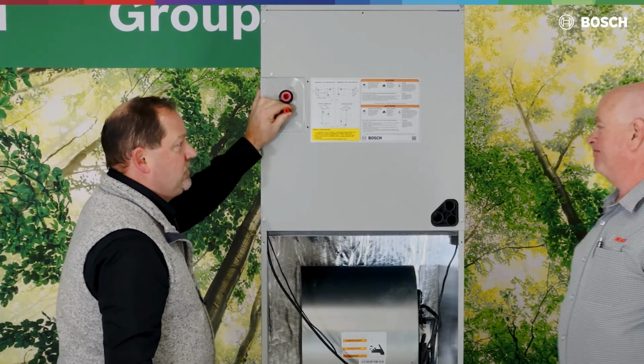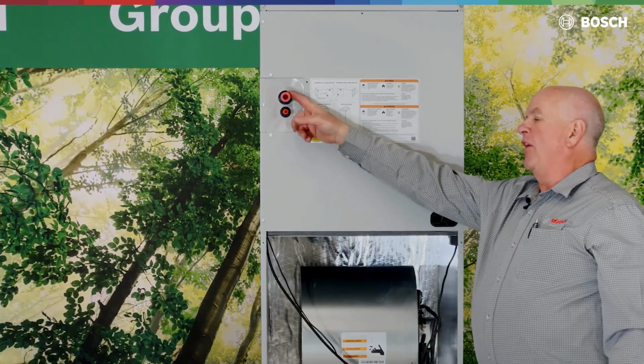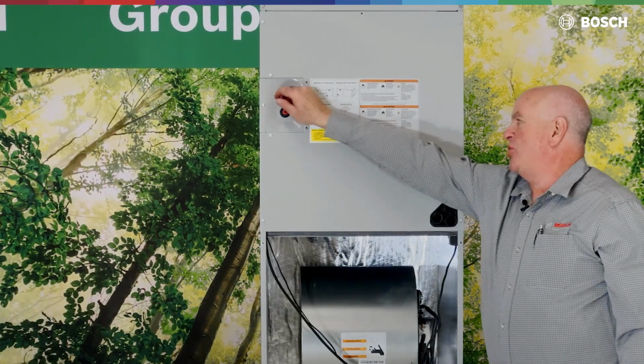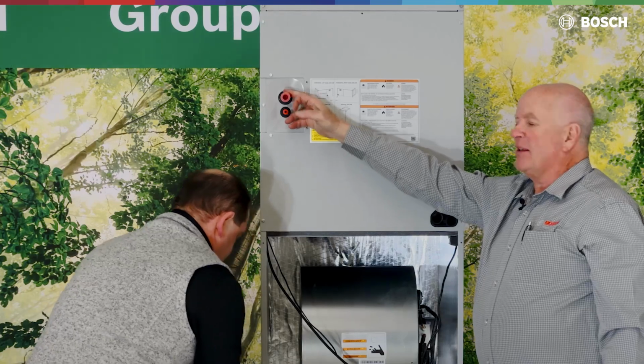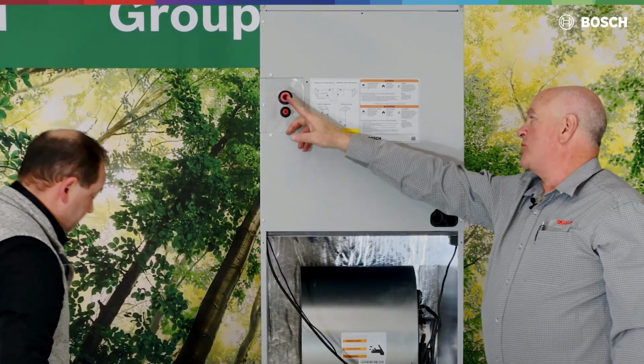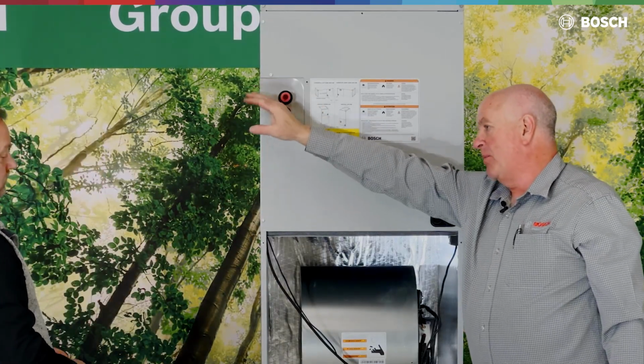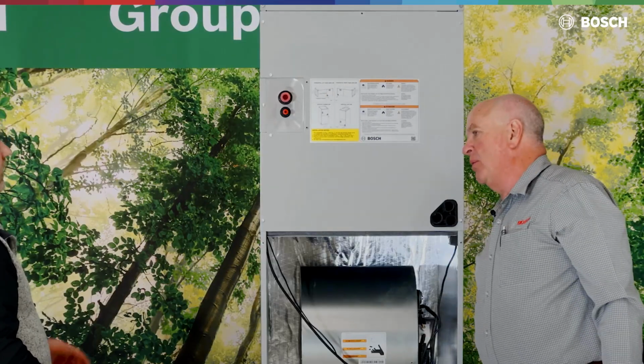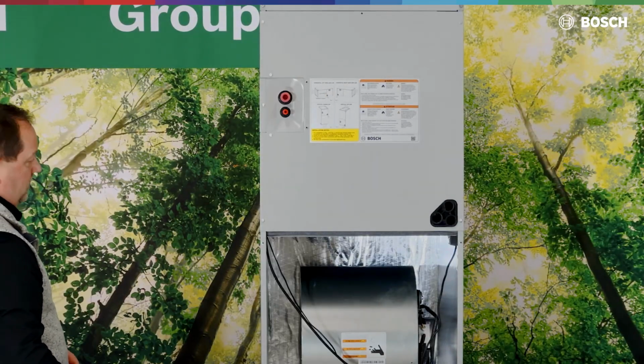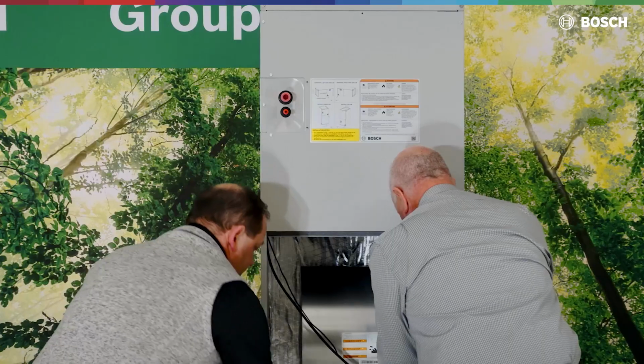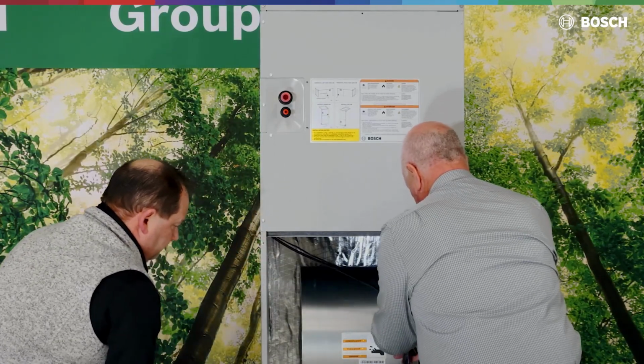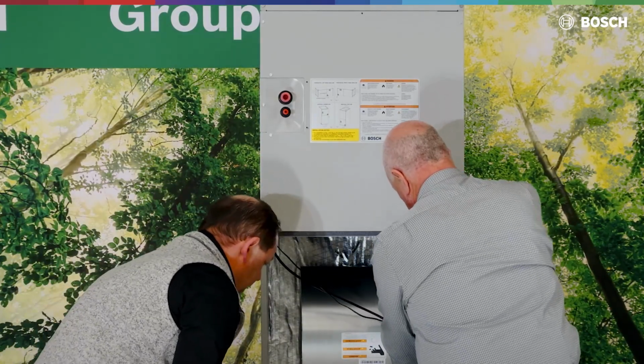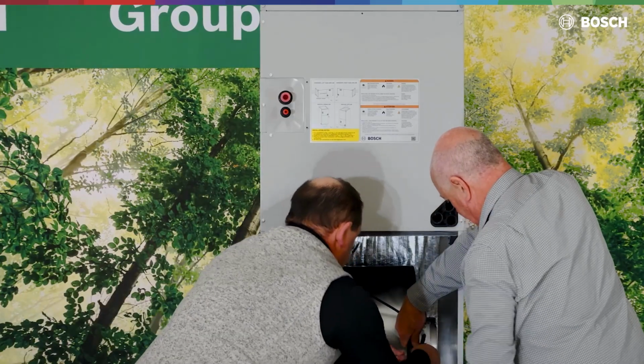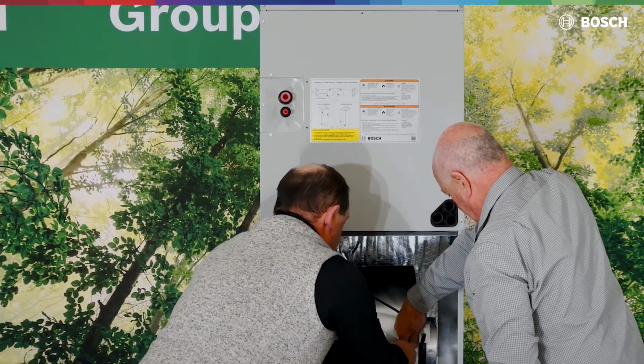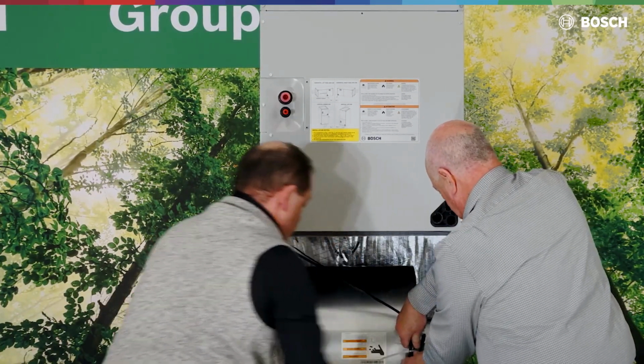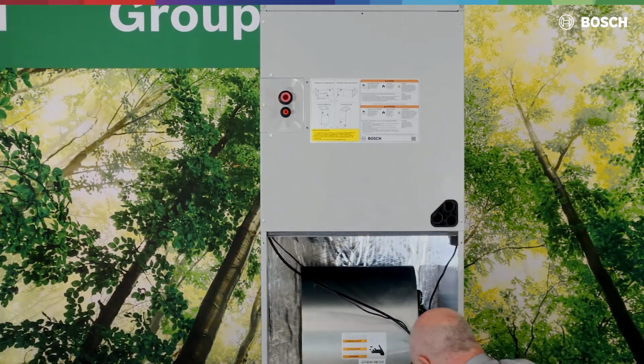A couple different styles. Now they're not made to go over the flare, so the swage. So if you were going to do that, you'll probably have to cut the swage off, or you can braze on a small piece of copper and then go Pro Press. But again, it's the heat issue at that point you need to watch. Okay, yep. So we got some wire ties in here. Just go ahead and tie this up a little bit so we don't get in the way of our fan. Nice and neat. Did you put one around there, Chris? And we'll put one down here and make this nice and neat.